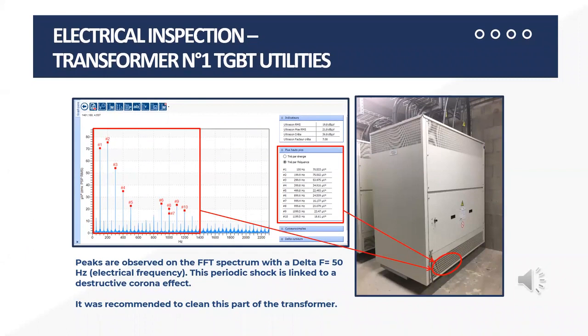Electrical inspection, always a great use of ultrasound, looking for things like arcing, tracking, and partial discharge corona. When we listen to electrical equipment, we're really expecting to hear next to nothing at all.